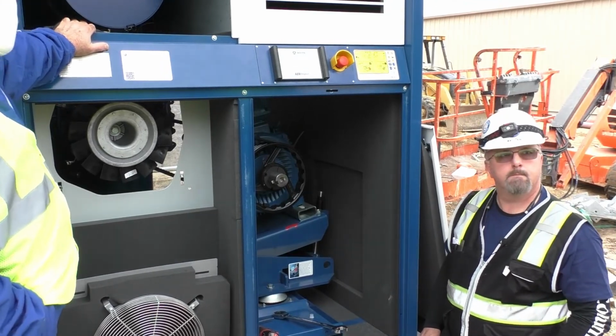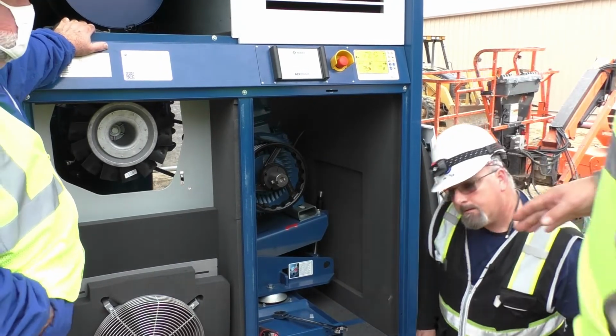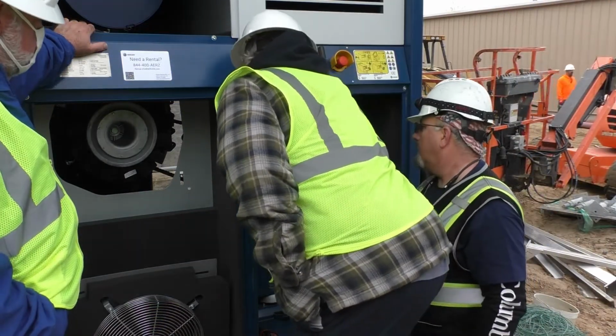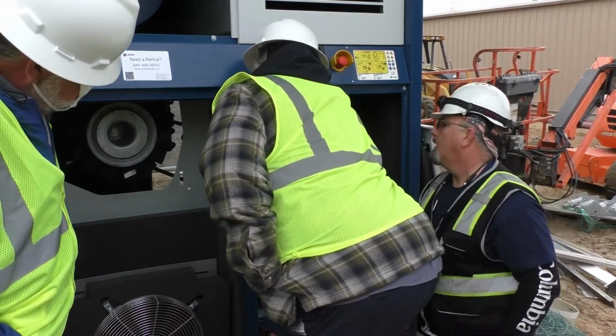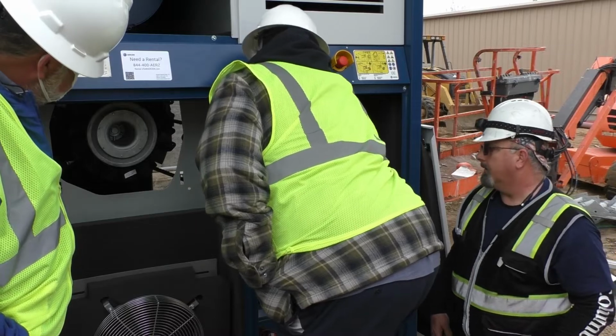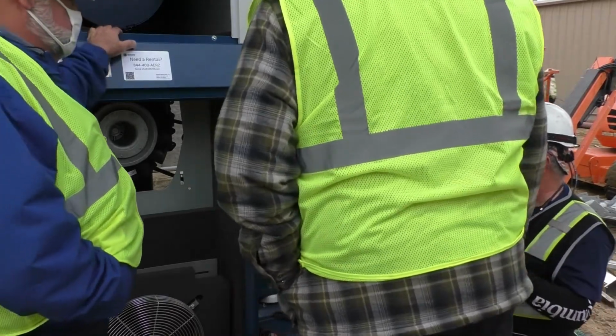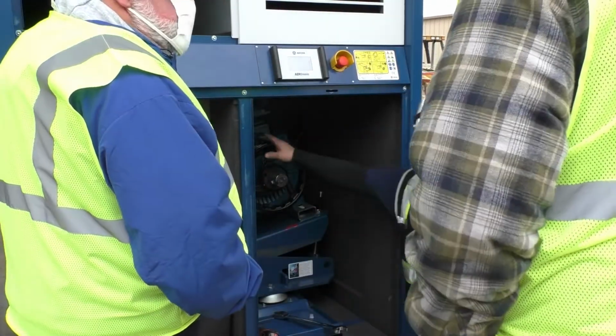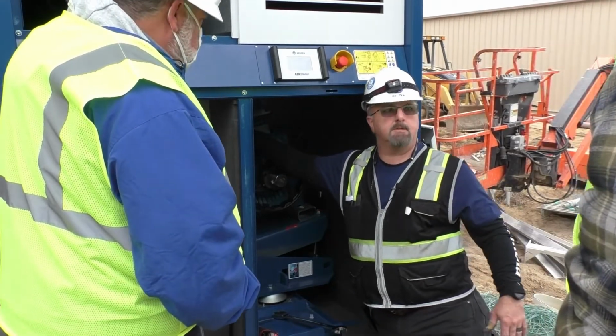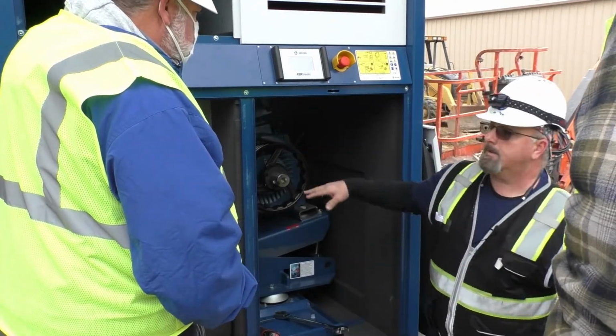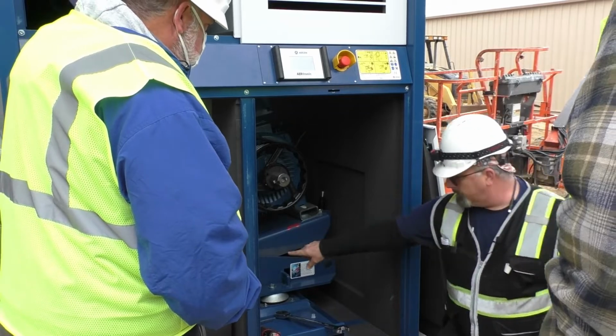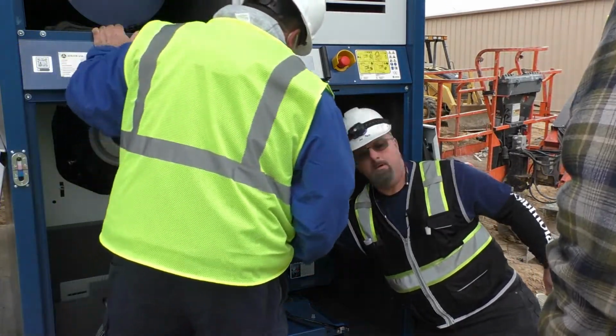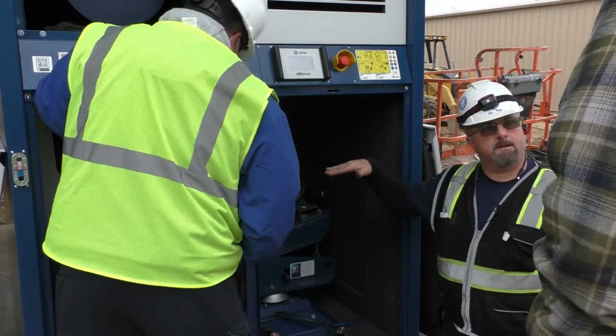So you don't go by like a deflection of, touch your belt and you see you have a little bit of deflection in there, like a 1/4 inch maybe? For doing the tension on the belts, no, you do not have to take a belt tension guide and check the tension on the belts. That has already been calculated, because if you look down here, you have a pivot point where this motor plate raises up and down. Okay.